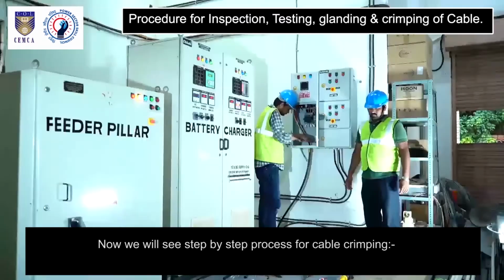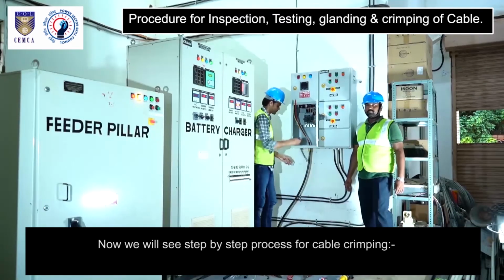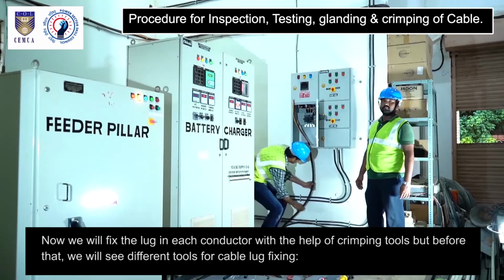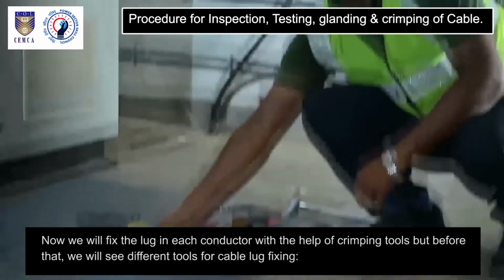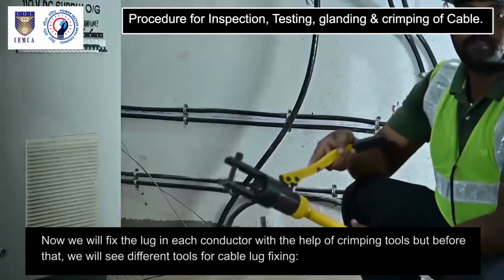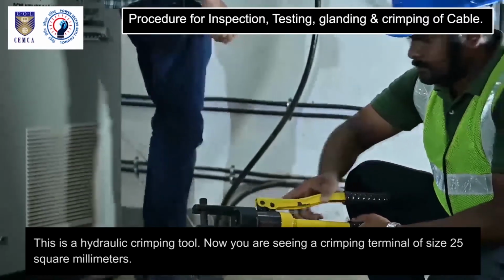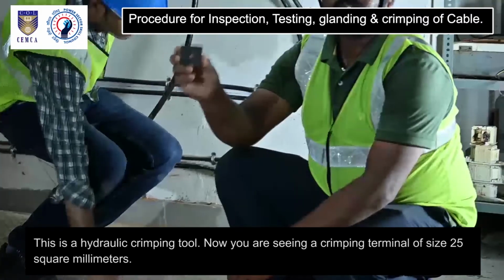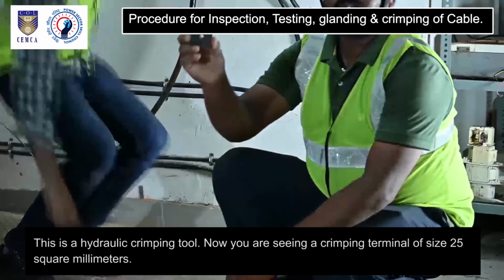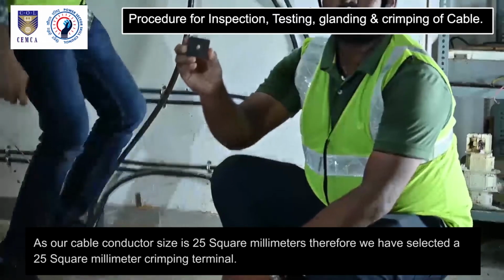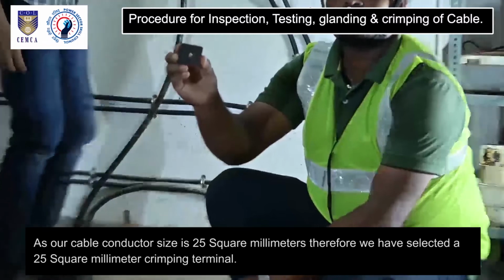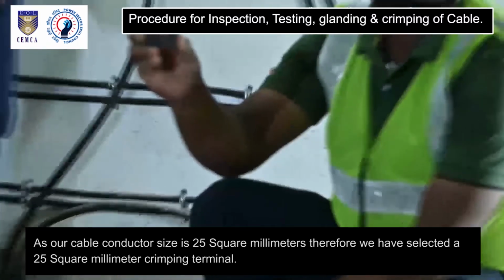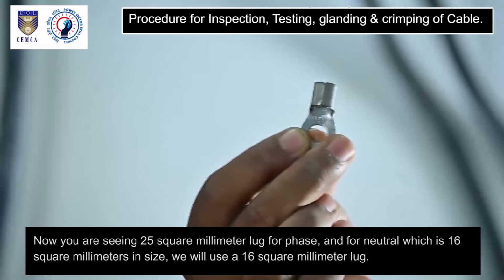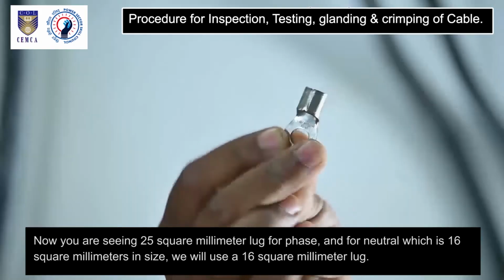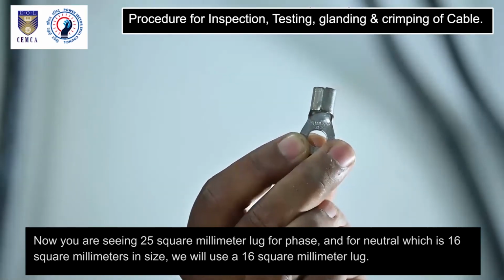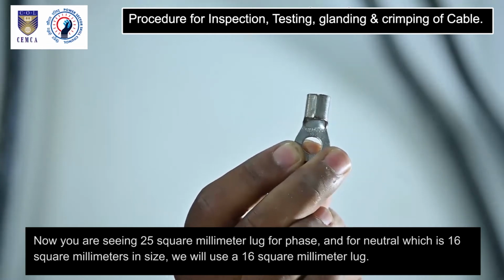Now we will see step-by-step process for cable crimping. Now we will fix the lug in each conductor with the help of crimping tools. But before that, we will see different tools for cable lug fixing. This is a hydraulic crimping tool. Now you are seeing a crimping terminal of size 25 square millimeters. As our cable conductor size is 25 square millimeters, therefore we have selected a 25 square millimeter crimping terminal. Now you are seeing 25 square millimeter lug for phase and for neutral, which is 16 square millimeters in size. We will use a 16 square millimeter lug.